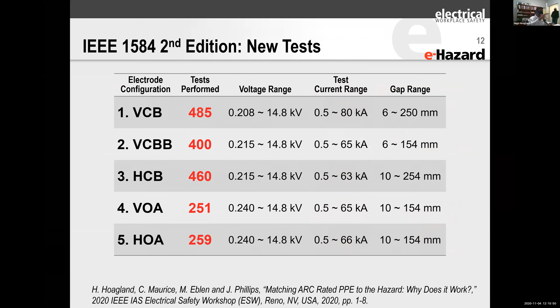Well, with the number of studies that we've done using the old 2002 standard as well as the 2018 standard, here's what we've noticed. When you have transformers of a certain size, on your 208 volt and 240 volt systems, the studies we did previously came up with energies which were less than 1.2. If you took the same equipment configuration today and plugged it into the newer standard, which is now more representative of the actual energy inside, you can see that the energies have now been corrected.